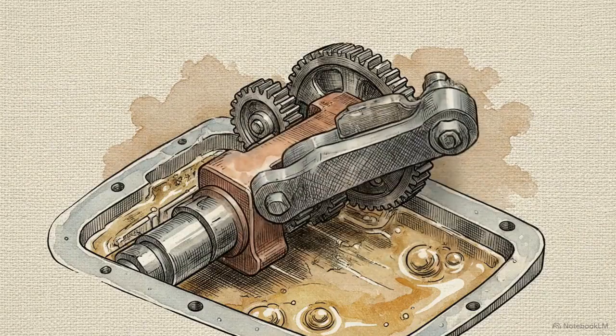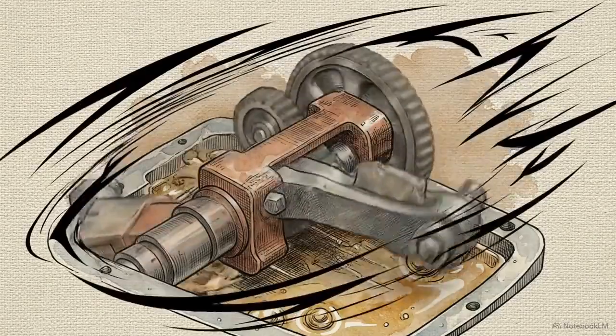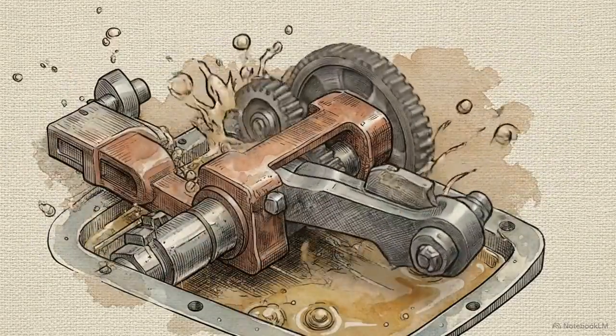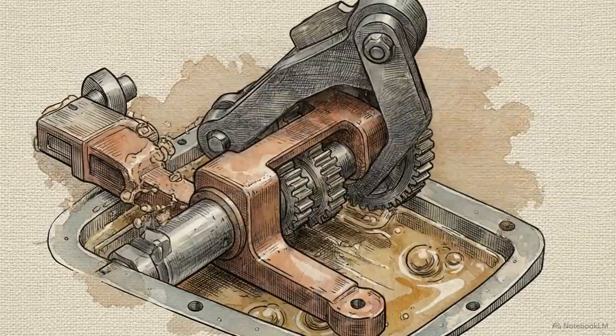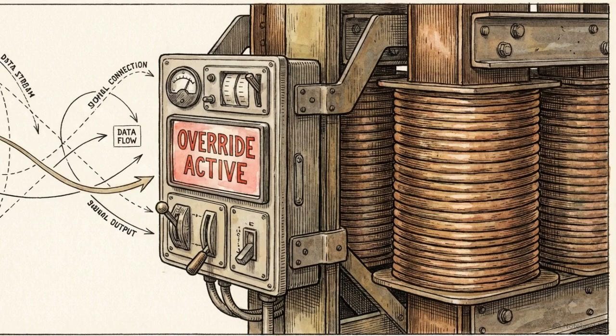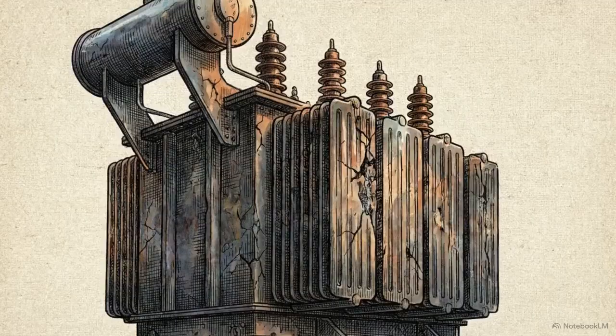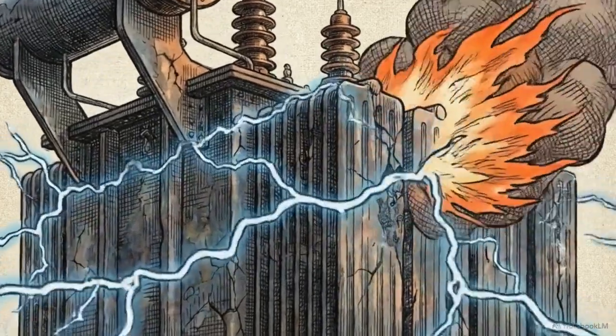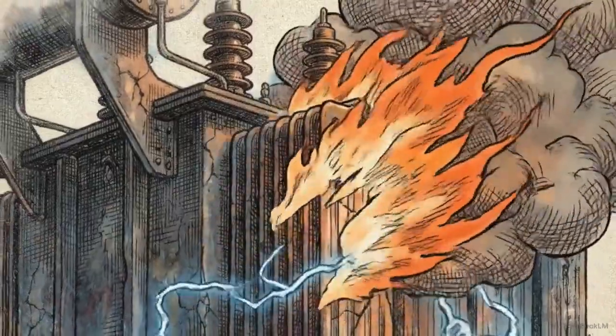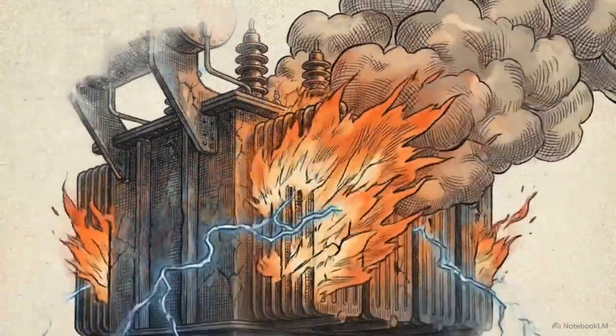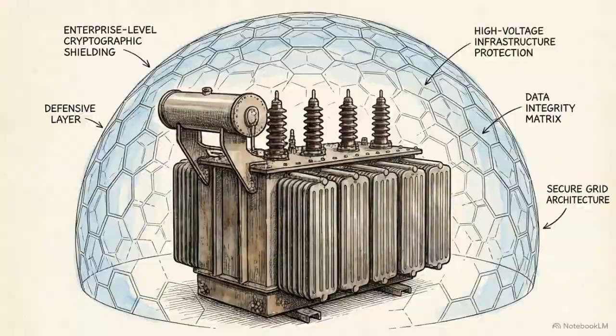Consider an IIoT system connected to an automated ecotap, a mechanical mechanism that automatically adjusts the voltage ratio of a transformer. It does this by altering the number of active coils. If a threat actor intercepts this connection, they can remotely manipulate the tap changer. Forcing an abrupt voltage misalignment at peak load physically overloads the grid, triggering a catastrophic fire and destroying the multi-million-dollar asset. Defending the physical asset requires enterprise-level cryptographic shielding and strict adherence to frameworks like ISO 27000.